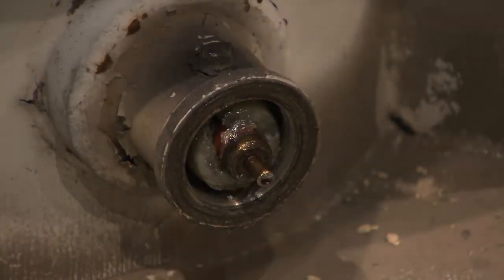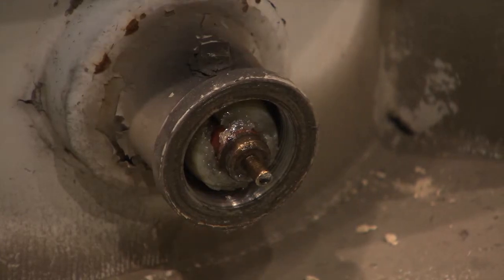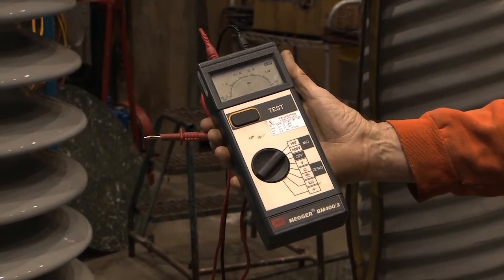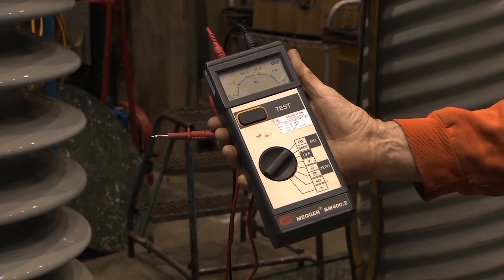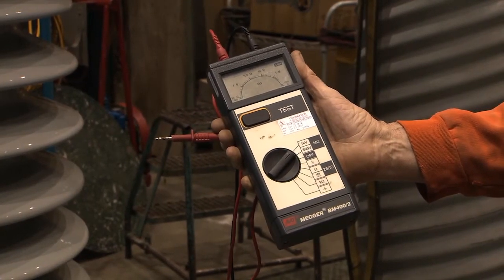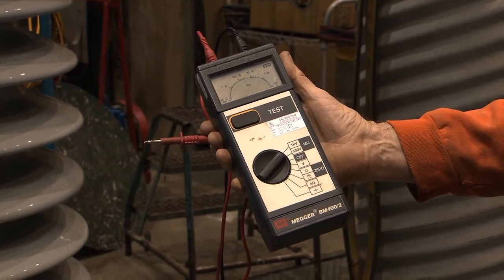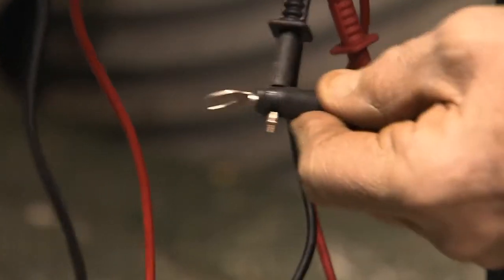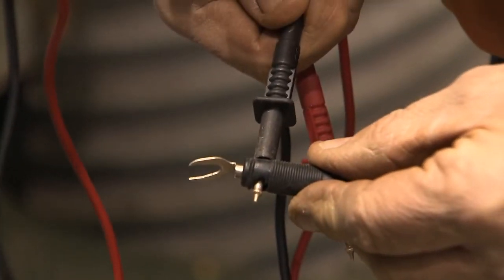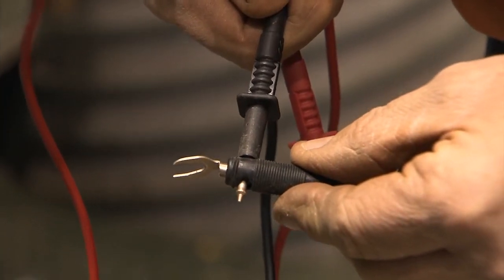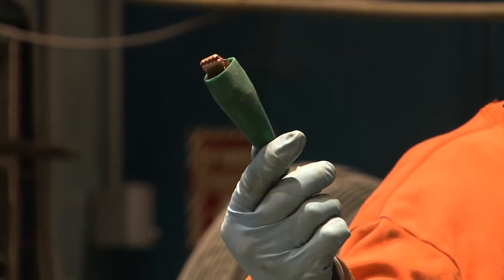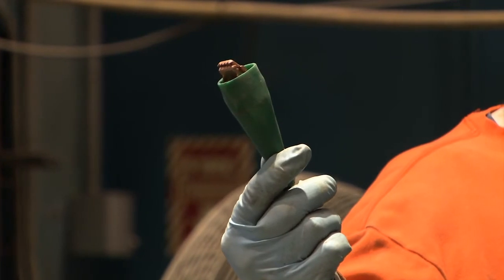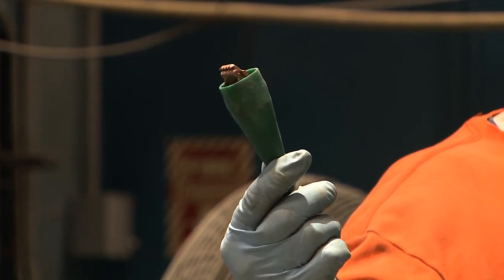In order to perform the initial electrical tests, the capacitance tap cover is removed so that the voltage tap, also known as the cap tap, can be accessed. The first test is performed using a megohm meter, or Megger. By connecting a cable extension to the black lead, the extended cable can be connected to the conductor core via the threaded rod extending out from the top of the terminal at the top of the bushing.